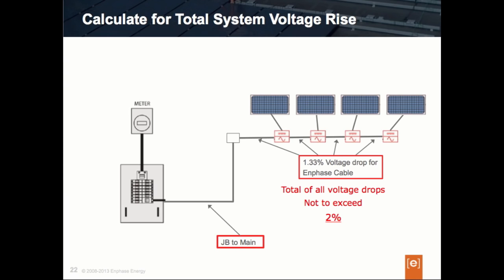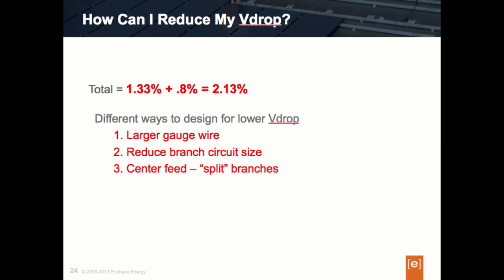So in our design, the voltage drop of the Enphase cable is 1.33%. Now let's say the wire size between the main panel and the junction box gives us a total voltage drop of 0.8% at 240 volts. Our total voltage drop on this circuit is therefore 1.33% plus 0.8%, which equals 2.13% end-to-end. That 2.13% is over our design recommendation of 2%, so we need to ask: what can we do to resolve this and get the design under 2%?